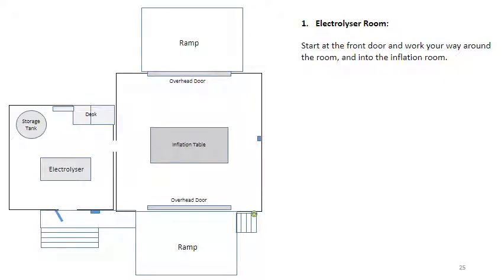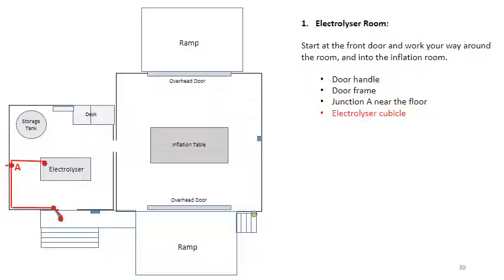In the electrolyzer room, start at the front door and work your way around the room and into the inflation room. First, check that the ground wire is properly attached to the door handle. Then check the connection to the door frame. Follow the ground wire down near the floor until junction A, which is under the window. Now follow the ground wire running up and over to the top of the electrolyzer cubicle. Then follow the ground wire going up to the top of the storage tank.